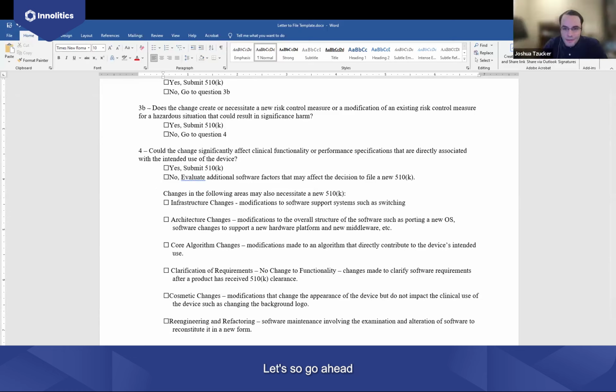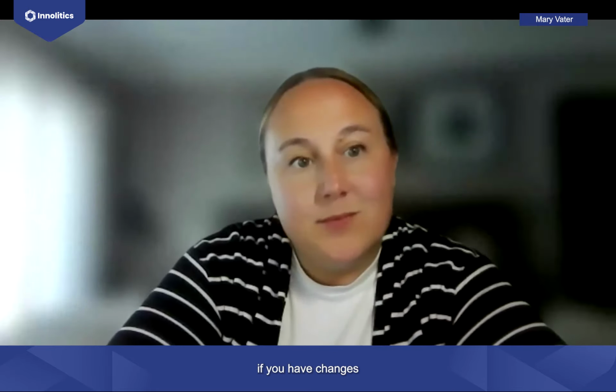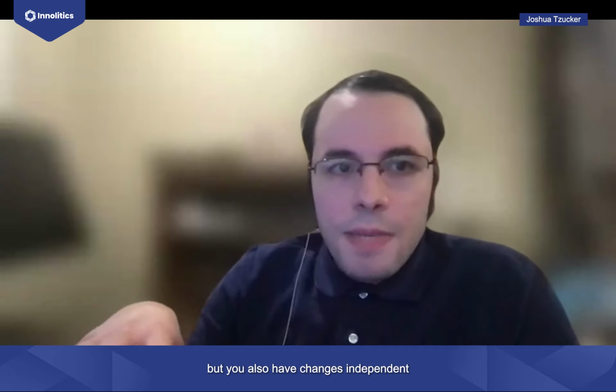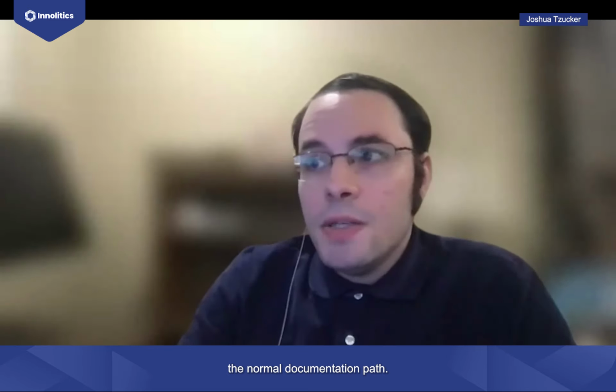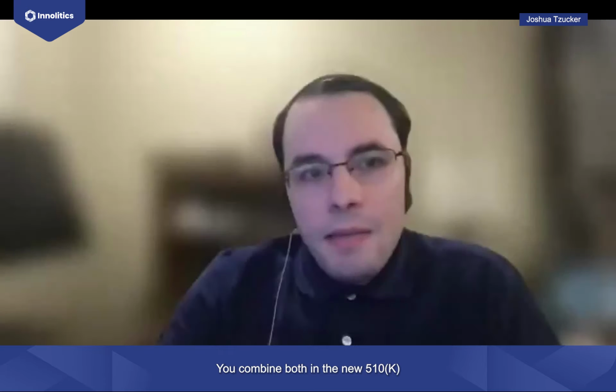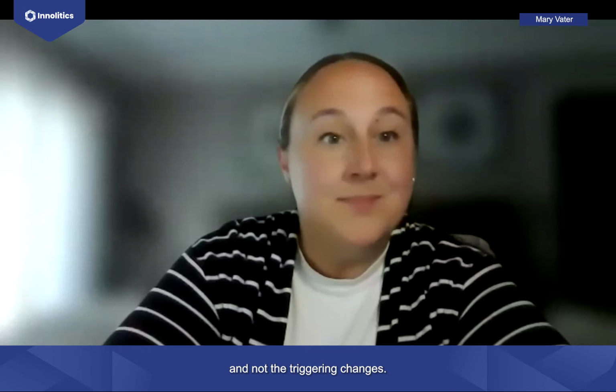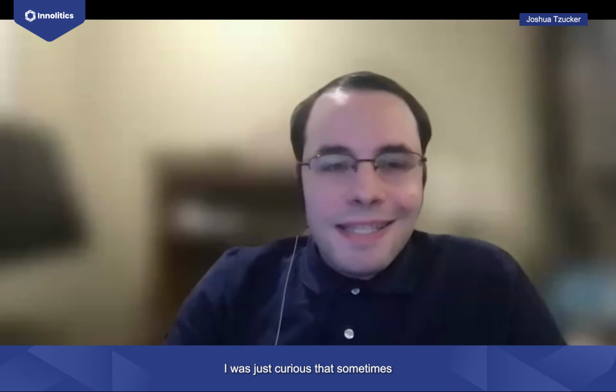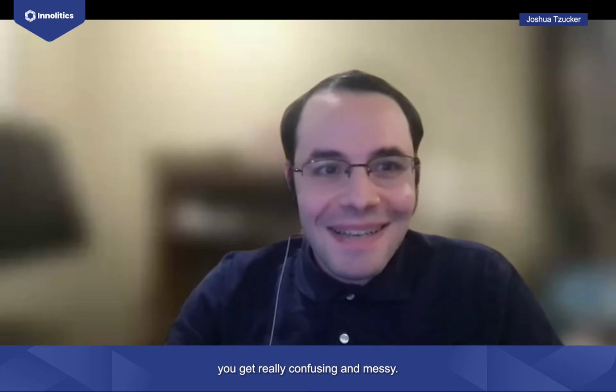I have a quick question. Go ahead. I might be misreading the guidance here, but one of the items talks about if you end up having to make it seem like you should submit a new 510(k). It sounds like they're saying if you have changes that trigger the 510(k), but you also have independent changes that would just follow the normal documentation path, you combine both in the new 510(k). But then it made it sound like you could make those changes that are not the triggering changes immediately. So I was just curious. That sounds like it would get really confusing and messy. Does that happen in practice, or what does that look like?